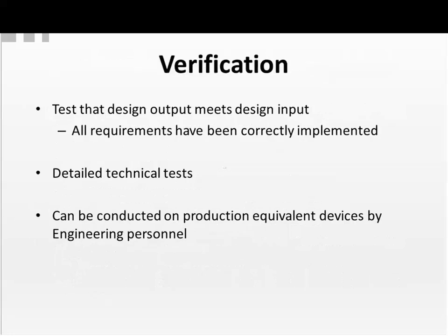Verification step. In the verification, we test that the design output meets the design input. Test that all requirements have been implemented and that they have been implemented correctly. Now, these are detailed technical tests, and these can be conducted on production equivalent devices by engineering personnel. You don't need to involve users or user groups for the verification. Strictly a technical test.